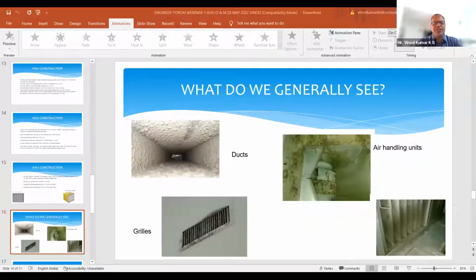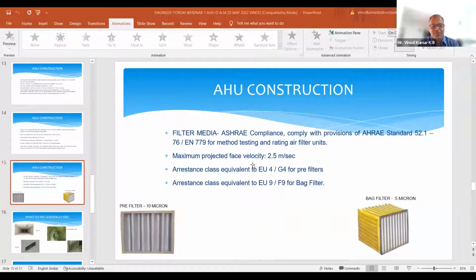Actually, in the filter case, the pre-filter is one that is washable. Normally, it's of a synthetic media that is easily washable and can be reused. And when you go for a bag filter or fine filter, it's not washable. You can only dust it using a blower or a vacuum cleaner. But generally what you do is you have differential pressure gauges, which you install before and after the filter. As I said, pre-filter one, fine filter one. You put a differential pressure gauge before and after the pre-filter, and you put another differential pressure gauge before and after the fine filter.